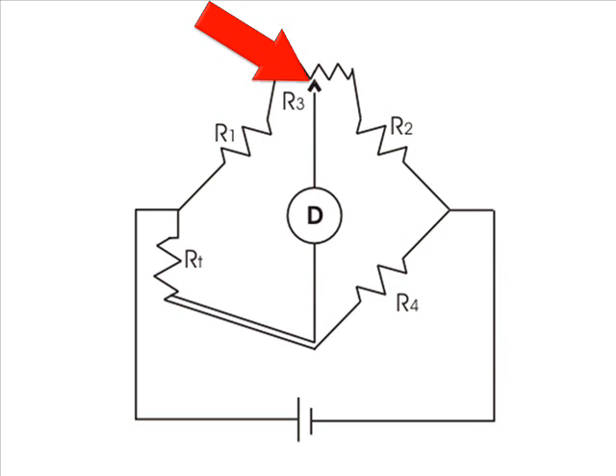But still an RTD circuit suffers from two major drawbacks. One, when current flows through RTD bulb wire, there would be I squared R loss which will generate heat, and this self heating of RTD coil may affect the actual temperature reading.